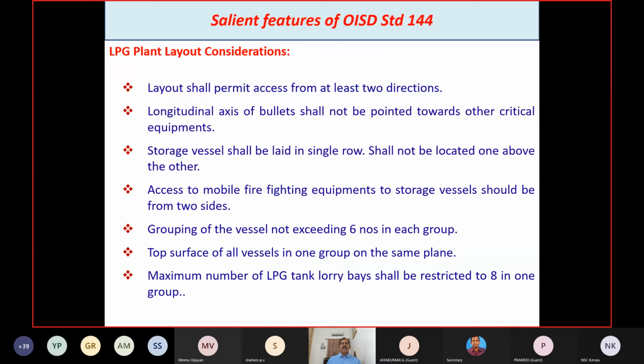Grouping of the vessels not exceeding 6 numbers in each group. The top surface of all vessels in one group should be on the same plane. The maximum number of LPG tank lorry bays shall be restricted to 8 in one group. The LPG tank lorry truck loading bays: the trucks should also be parked facing towards the exit, and there should not be any reversing or turning during any emergency.